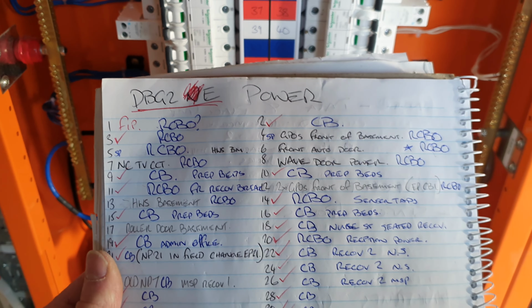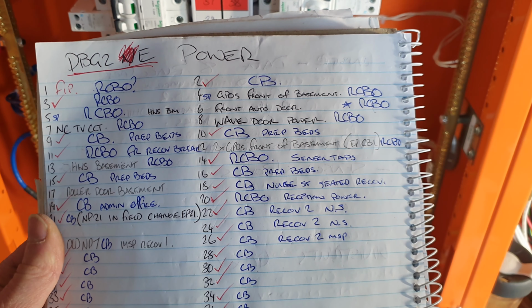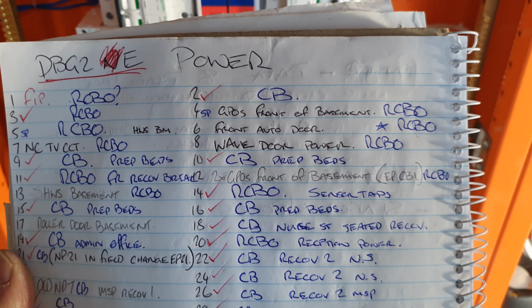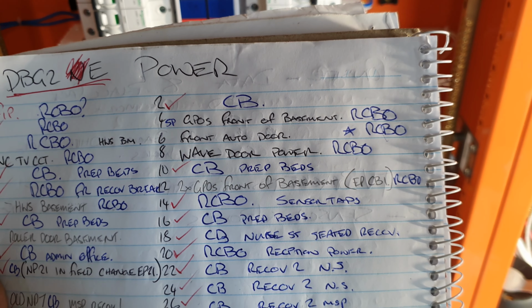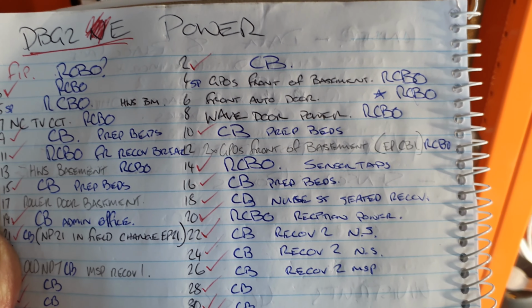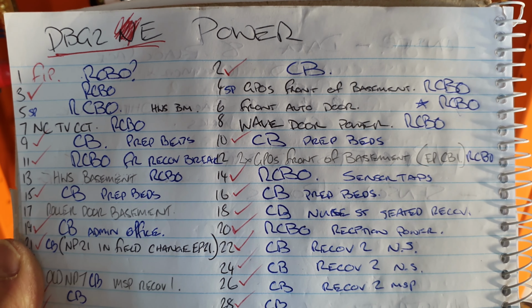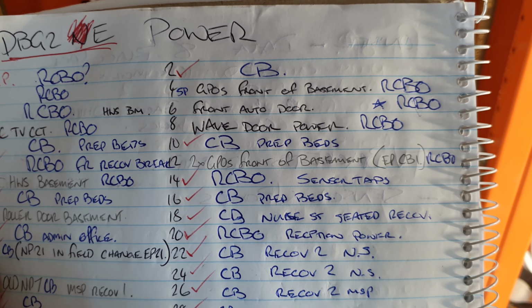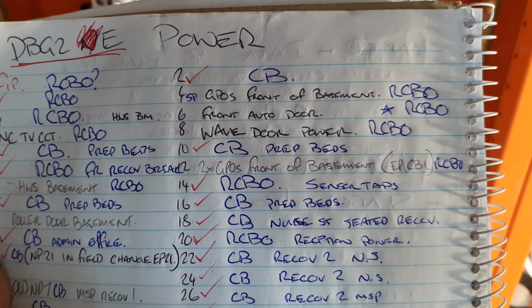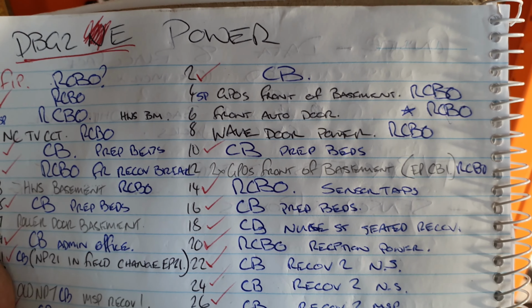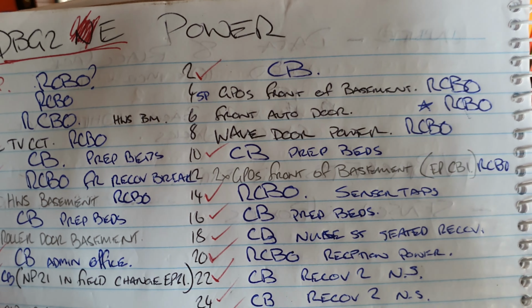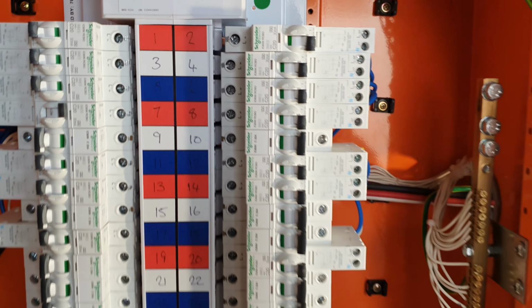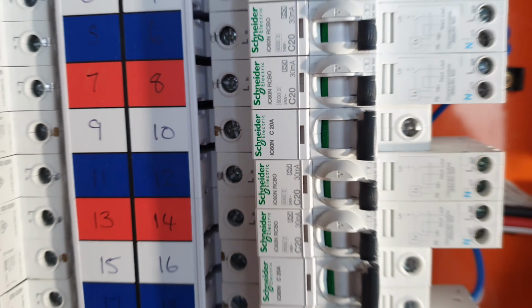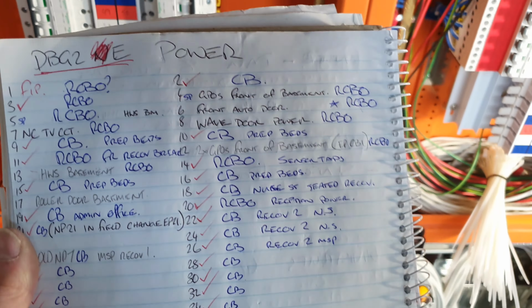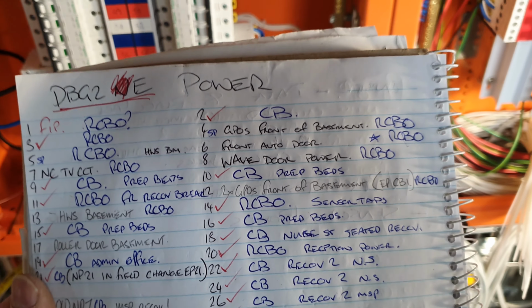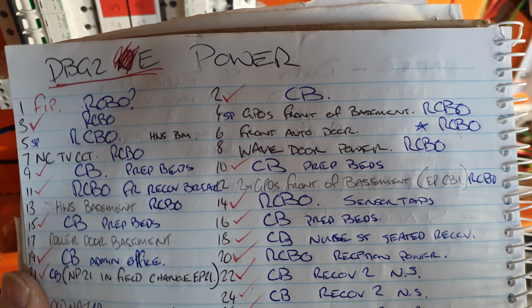I went through the rest of the list and checked. We've got some GPOs in the basement on number 4, that needs to be on an RCBO. Then down to number 10, which is a circuit breaker, and those are the preparation beds pre-surgery. For that one, it's a medical service panel, so you have a circuit breaker at number 10 that goes out to the field, and then there's an RCD in the field to protect the outlets that medical services panel is feeding.